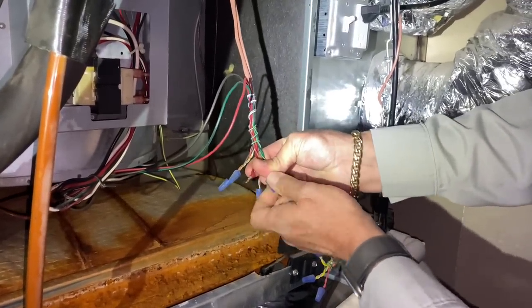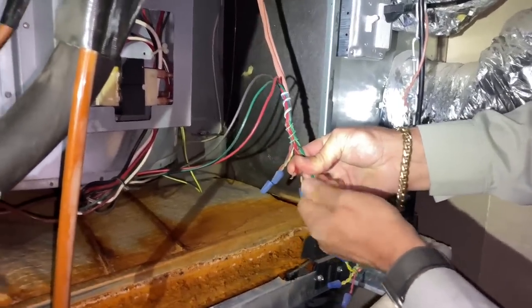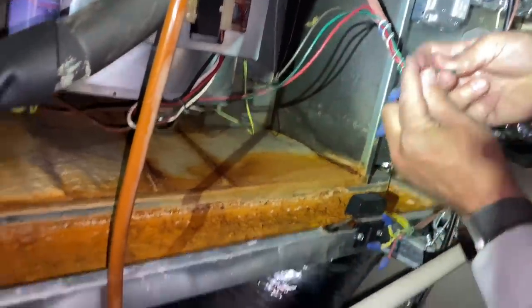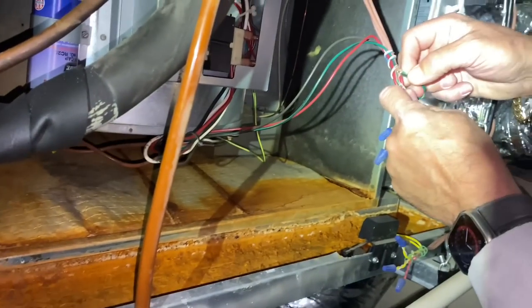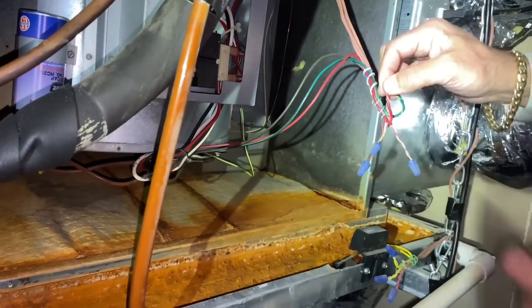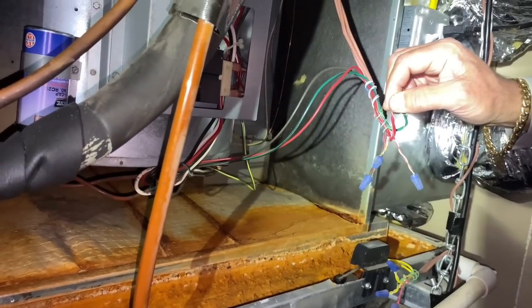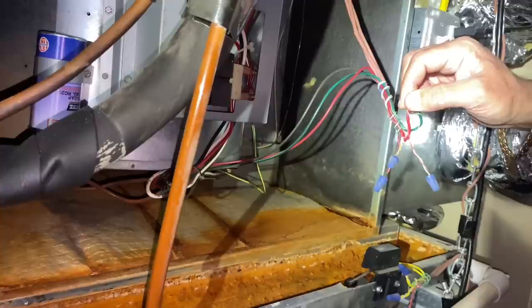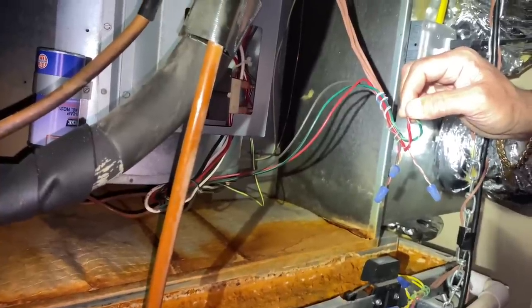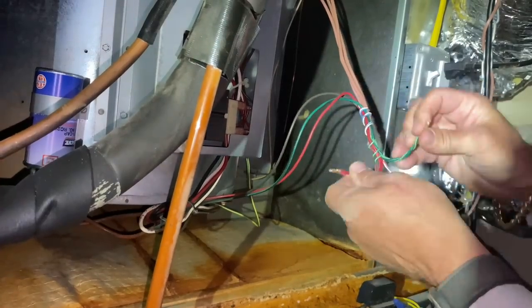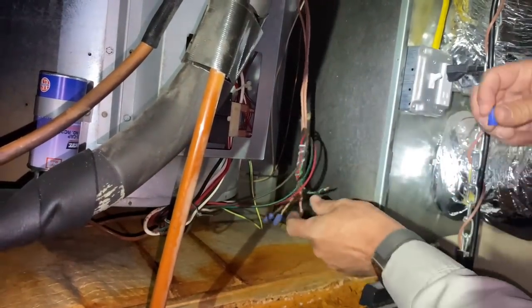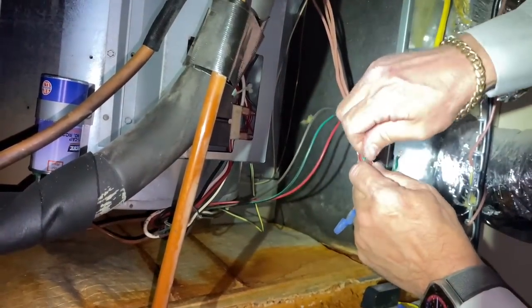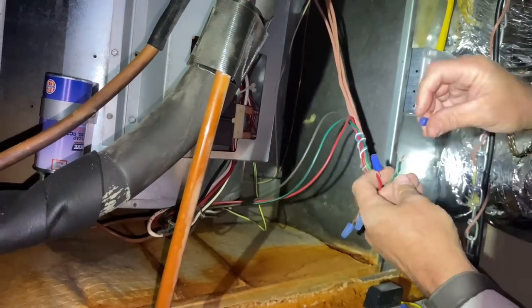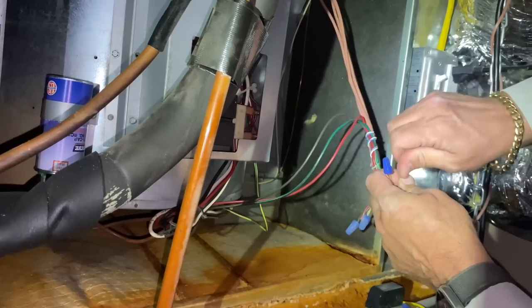And while we're doing this, take a look at the bottom of this air handling unit, you can see it's all rusted there. It's because the drain was clogged and flooded out the system. Okay, let's put that right there, let's see what we got. We got nothing, nada. It does not sound good. What was clogged? Oh no, there's a piece of foam in the blower, not really a big deal, but nothing there.